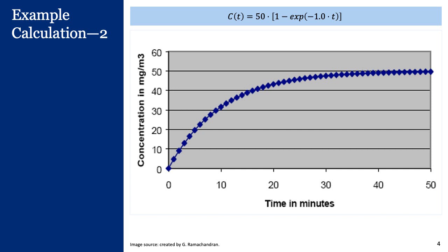But then as enough contaminant molecules enter the room air, now the cleaning mechanism actually shows its effect. So we can see that the rate at which the concentration is increasing in the room is decreasing. So we can see a gradual bending of the curve. And so what this means is that the contaminant removal mechanisms are also now beginning to have a significant noticeable effect.